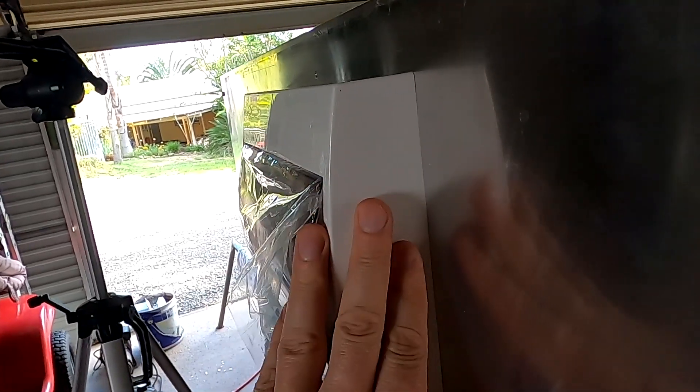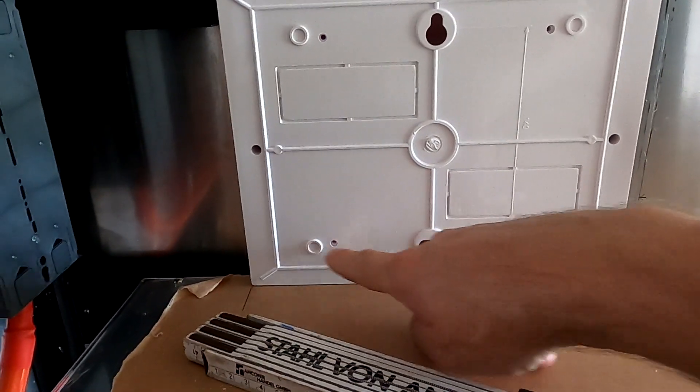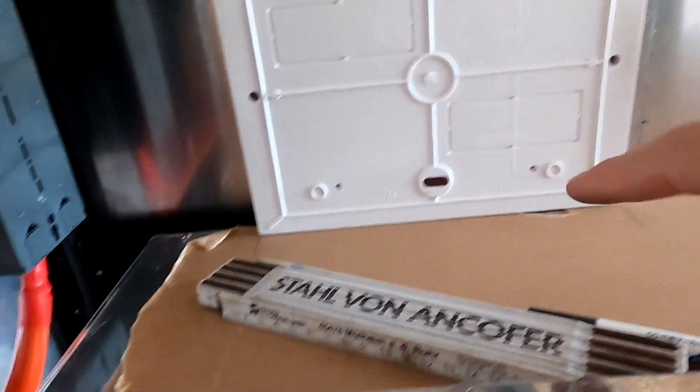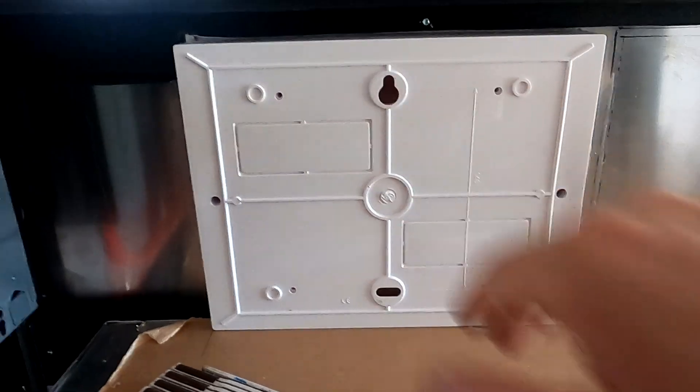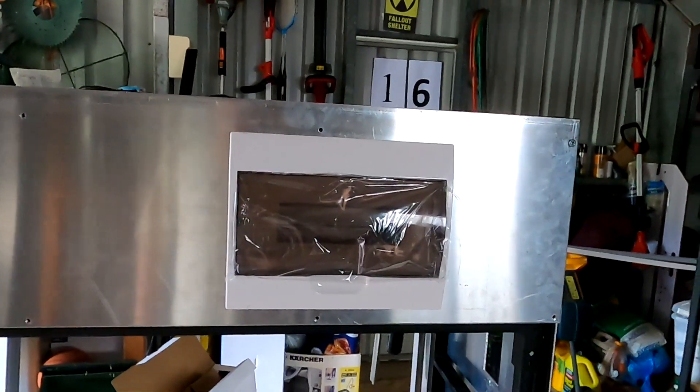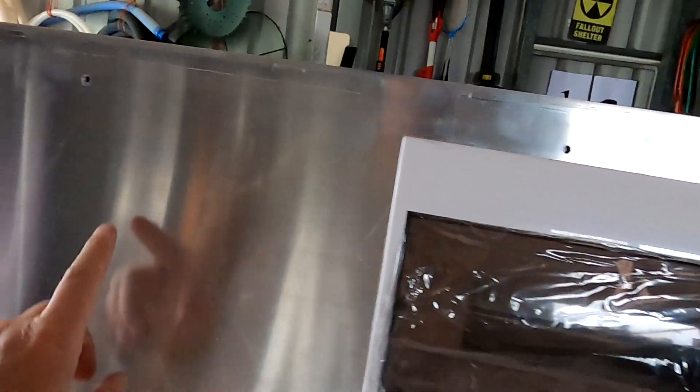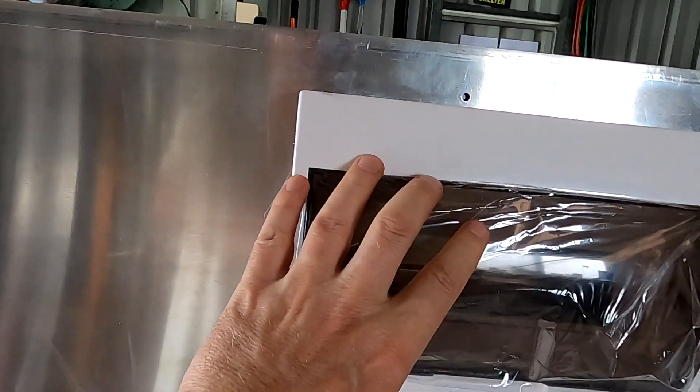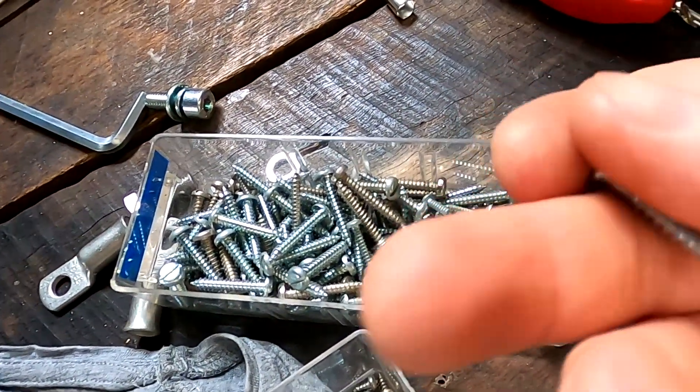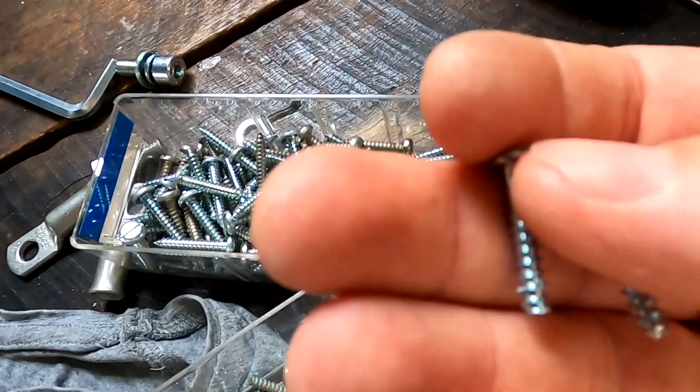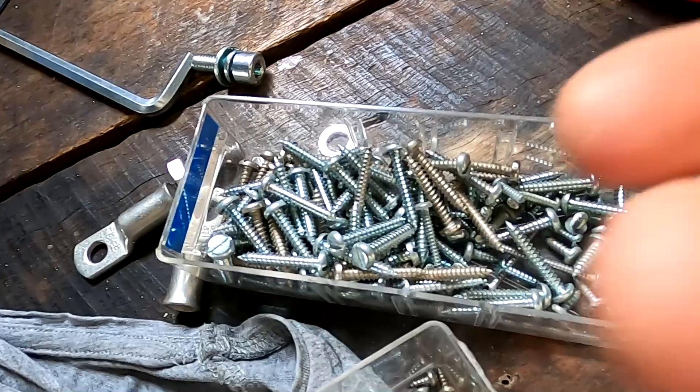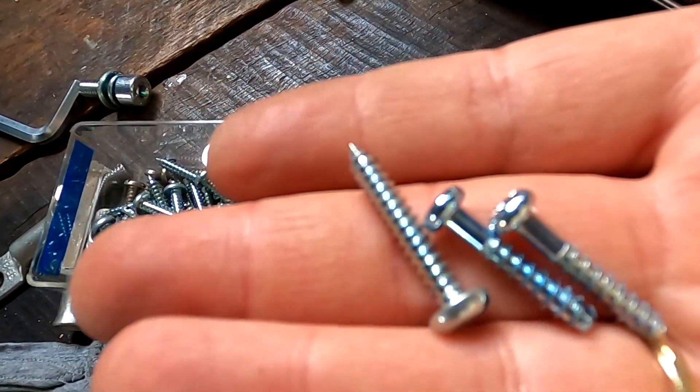If it's mounted on the outside of the panel here, it is fairly thick. And this is only half of the size now which sticks out when we drill all our holes here and have the cables connected to the circuit breakers inside and everything is covered. Well, I haven't got a second switchboard here, but I will make the cutout now the same as this one and then we use this one here as a template to see if it would fit here as well. The only thing I had to modify is these screws here, they were a tiny bit too short, so I just took some longer ones here and everything is good now.